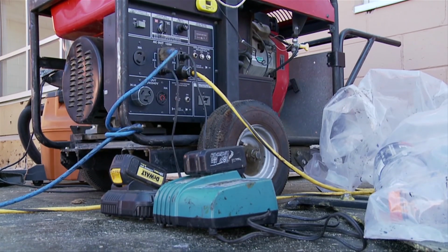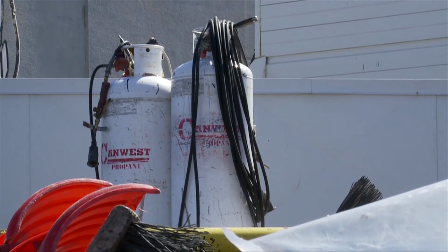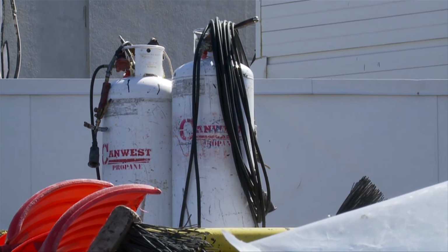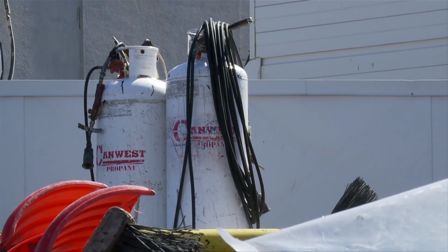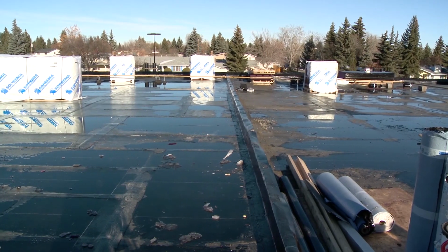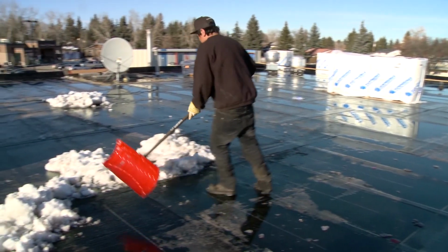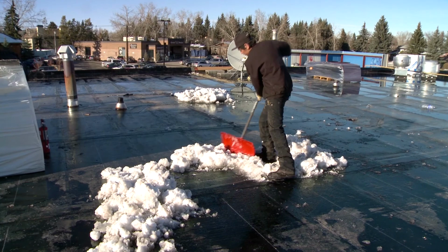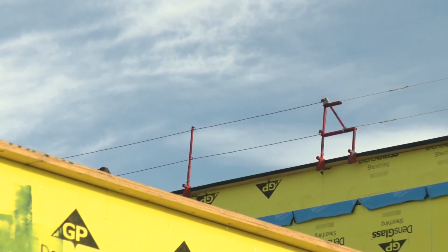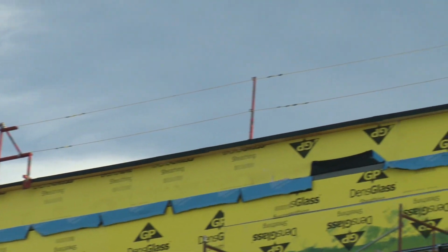Never operate portable generators or electrical equipment near propane cylinders, as leaking propane vapor collecting on the roof surface could be ignited by an electrical spark. Polyfilm surfaced modified bitumen base sheets become extremely slippery and may be a falling hazard when wet, snow, or frost covered. Install guardrails or use fall protection when working near the roof edge at all times.